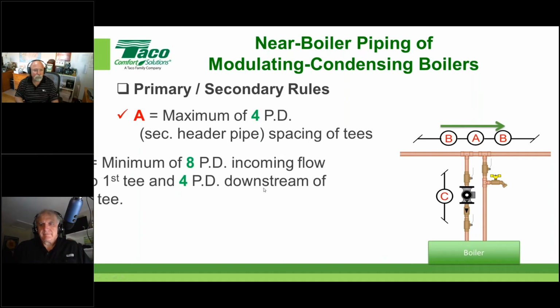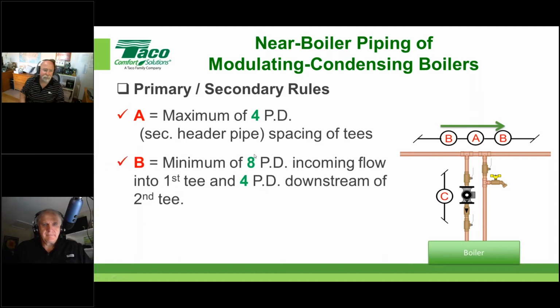Here we go. So the B note is the opposite of that because it says minimum. Okay, so notice the flow direction is coming from left to right on my screen. I believe it is on yours as well. So this distance before this first tee wants to be as long as possible at a minimum of 8 pipe diameters. What's 8 times 2? I would need this to be a minimum of 16 inches if this was a 2-inch pipe. Do you see the point there? Okay, once we've already gone through the first tee, the downstream side of the second tee can drop to 4 pipe diameters, half of what it was coming in. I'll show you another picture that'll help drive that home as well.